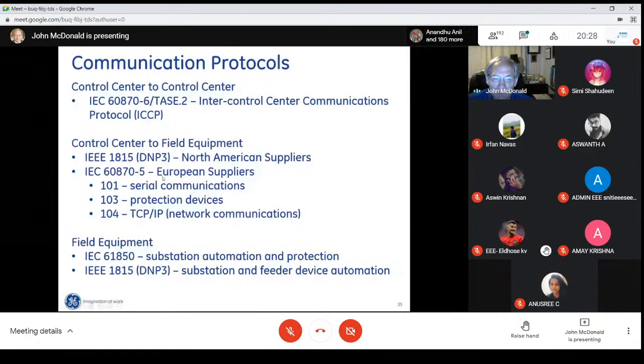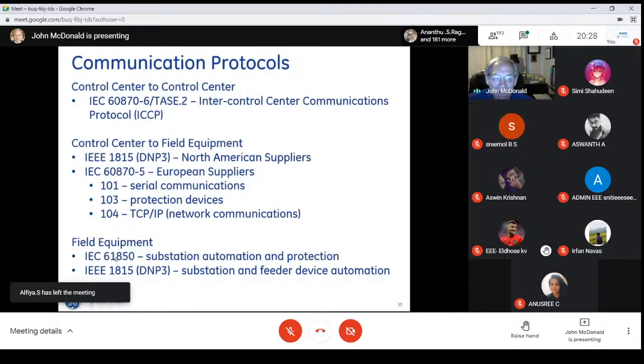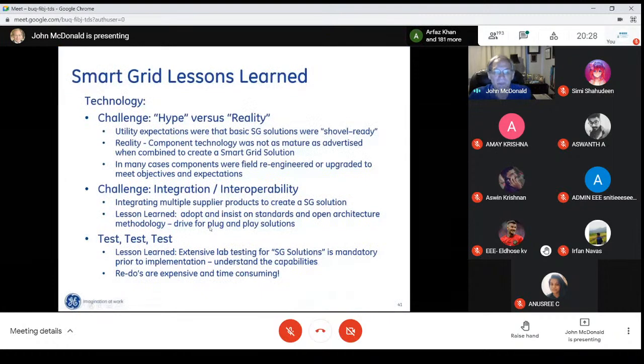European suppliers prefer to use IEC 870-5-101 for serial and 104 for network communications. Now, if we're within the field, IEC 61850 is the worldwide standard for substation automation and protection. But in North America, we still use a lot of DNP3, or IEEE Standard 1815, for substation and feeder device automation. So let me finish with a few slides here, and then we can have questions.